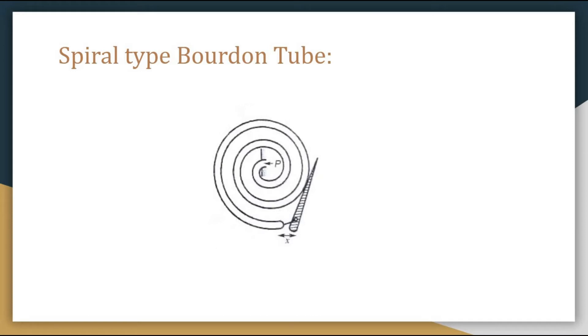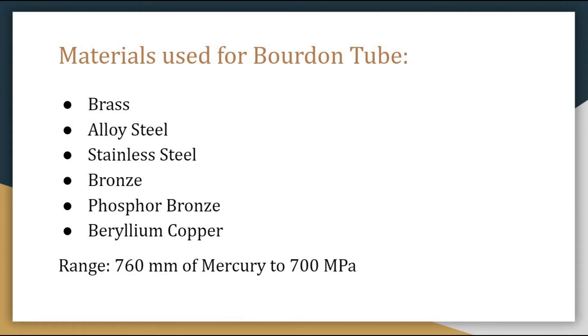So the sensitivity is greater in the spiral type Bourdon tube compared to the C-type Bourdon tube. Again, in the spiral type we observe displacement and measure pressure in terms of displacement. The materials used for construction of Bourdon tubes are brass, alloy steel, stainless steel, bronze, phosphor bronze, beryllium copper, etc. The range it covers is 760 mm of mercury to 700 megapascals.